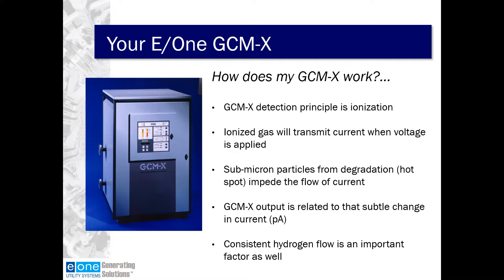The hydrogen goes everywhere in the generator — around and through cooling passages, in the rotor and the stator, behind the stator, around the end windings, through heat exchangers, around the bushings and leads, everywhere to the inside edge of the seals. The GCMX detects overheat anywhere that the hydrogen touches, so it's very much a global detector inside of the generator. Under normal operation, there are no submicron particles from degradation in the cooling gas of the generator.